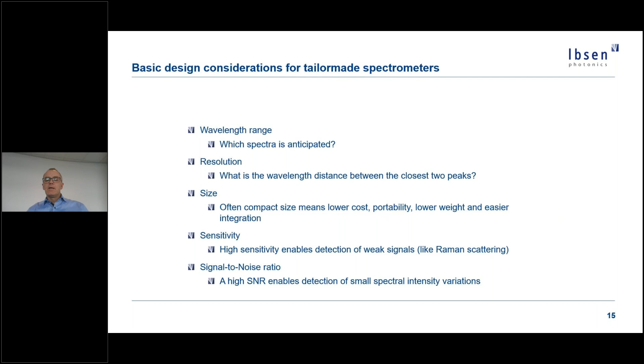Often it's desirable to go for as compact a spectrometer as possible, as this will often reduce the cost and weight, enabling portable instruments and/or instruments that are easy to fit into place in the factory. Raman scattering is a very weak process, so the spectrometer should in general have very high sensitivity. For some applications, the signal to noise can also be critical, but for Raman, it's often sensitivity that is most important.